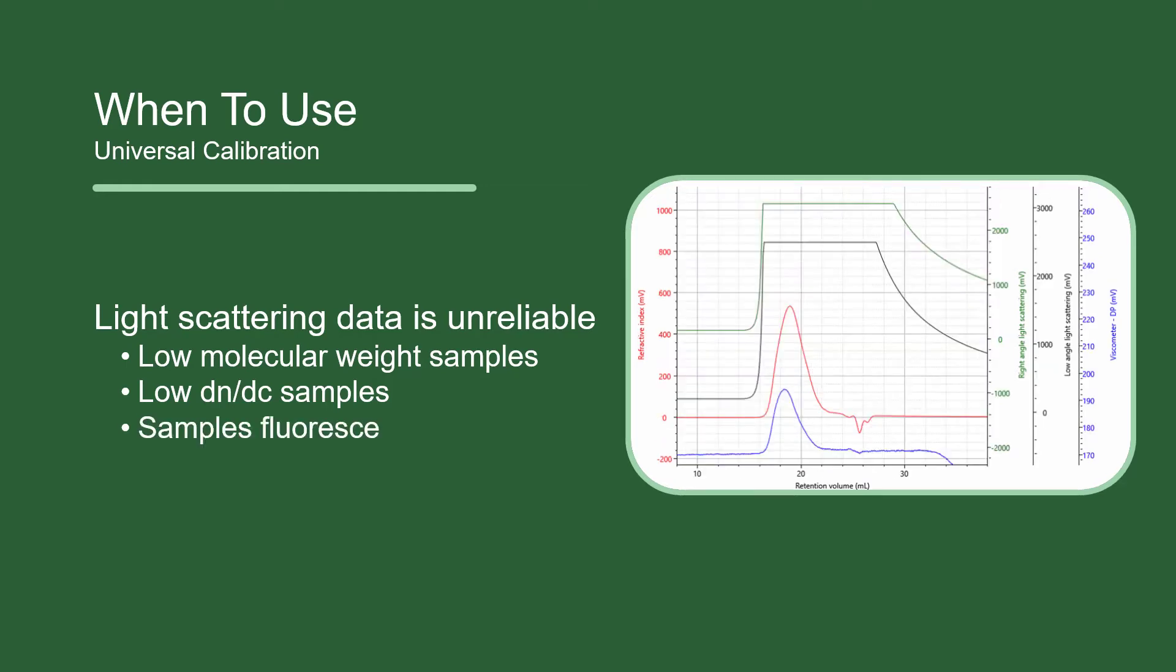Additionally, samples that fluoresce distort the light scattering response, typically in the positive direction. If you're working with a conjugated material and using light scattering to calculate molecular weight values that seem way too high, this could be the reason. Universal calibration can serve as a nice alternative in these situations.